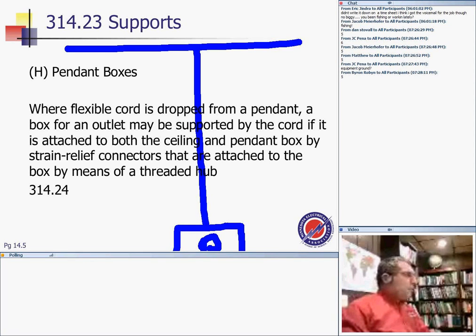Flexible cord. It's not a wiring system. It's a cord dropped from a pendant. A pendant for an outlet may be supported by the cord, no problem, if it's attached to the box in the ceiling and the pendant box by a strain relief. So what they do is they put a strain relief on these here and on these connectors that are attached to the box by means of a threaded hub.